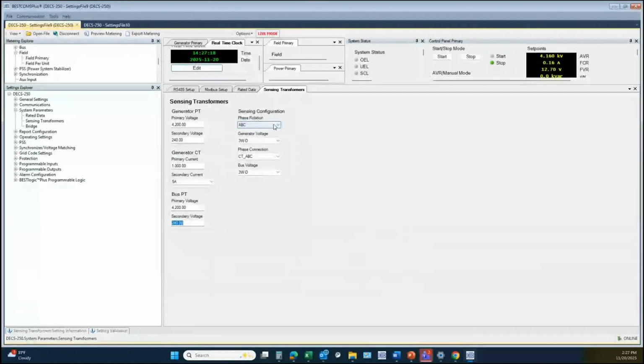ABC rotation becomes very critical to make sure this phase rotation is set correctly when you are paralleling. If you have that set incorrectly, then you will have paralleling complications. 3-wire delta or C to A for a 2-wire voltage sensing option. 3-phase CT or single-phase B-phase CT. Again, this is DECS 250. Some of these settings are slightly different with the 450.